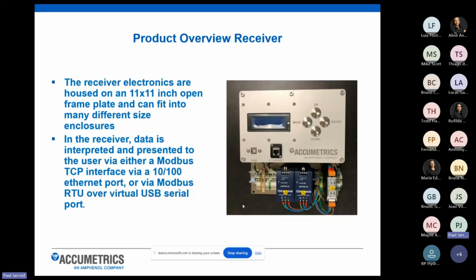And then the receiver does provide you with a Modbus TCP output. This is more industry standard from customer feedback we've gotten, that they are used to seeing the 8 channels of temperature data come across on Modbus. We do have the capability to do digital to analog conversion and provide analog outputs on this system, but most of our customers have asked for just a Modbus TCP digital output.